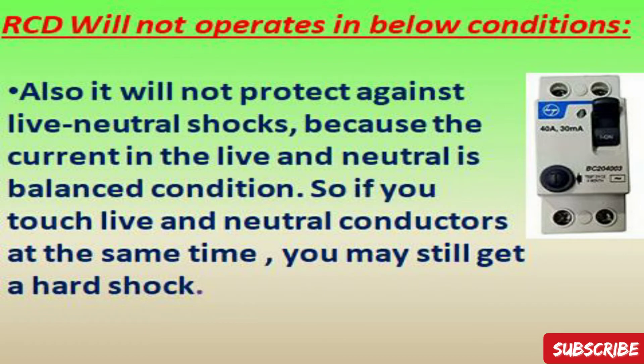RCD will also not protect against live-to-neutral shocks. This is very important: because the current in the live and neutral is in a balanced condition, if you touch both the live and neutral conductors at the same time, you may still get a hard shock, and this RCD won't trip.